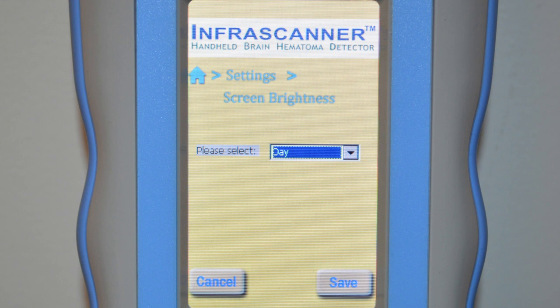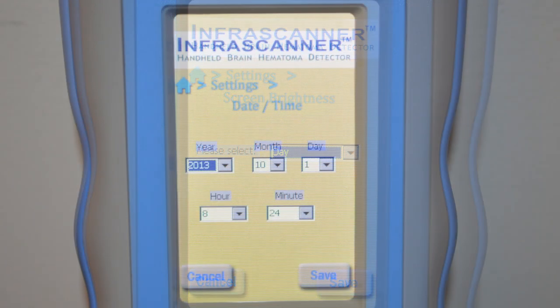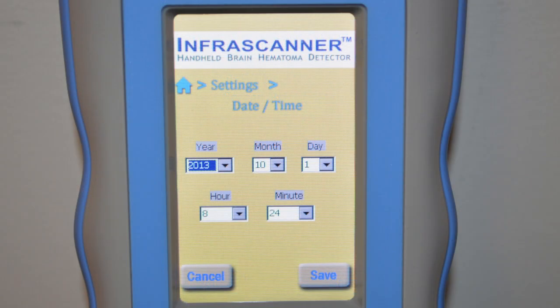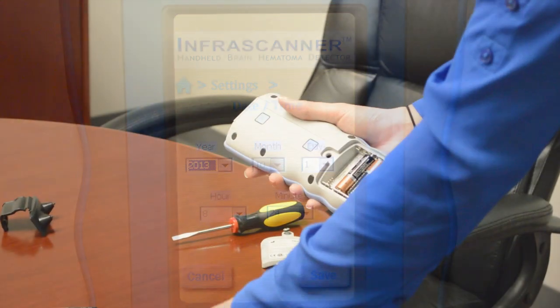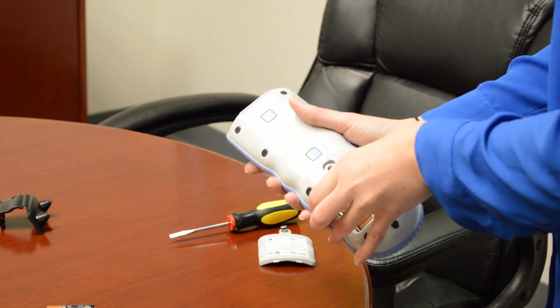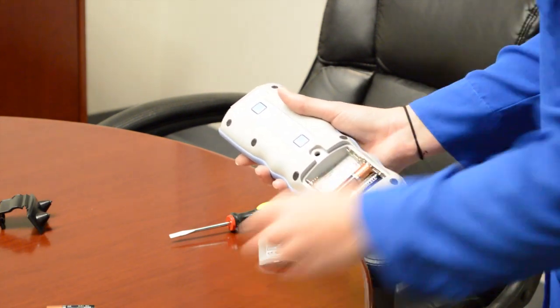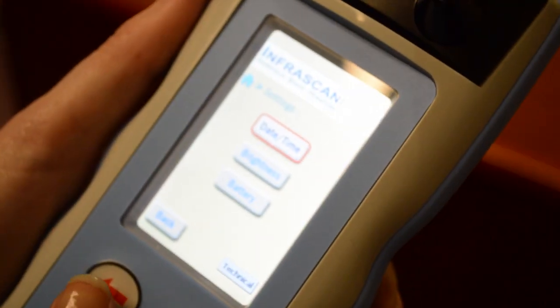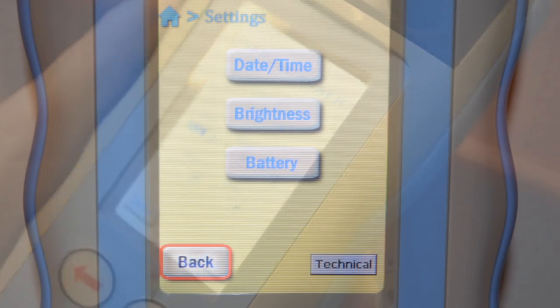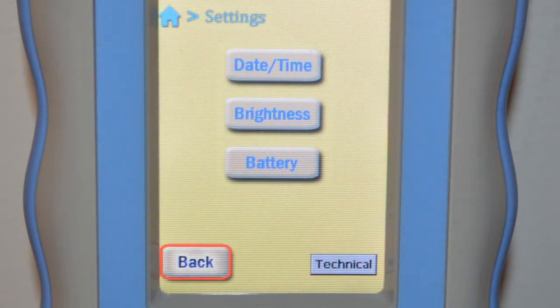The brightness screen is essentially a military application, allowing you to select night or day by using the up-down arrow keys to select. The date and time screen gives you the year, month, and day, along with the hour and minute. When AA batteries are being used and are taken out, the Infrascanner shuts down completely. If the batteries are not replaced right away, the user will have to adjust the time and possibly the date here. The technical button on the lower right is for technician use only.